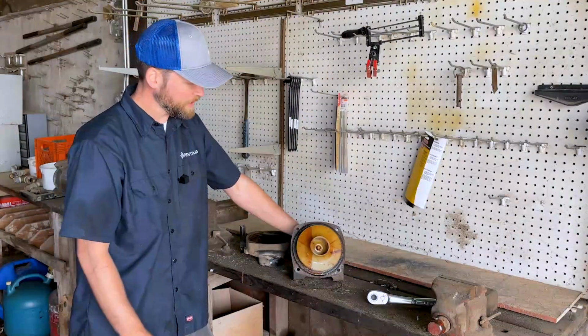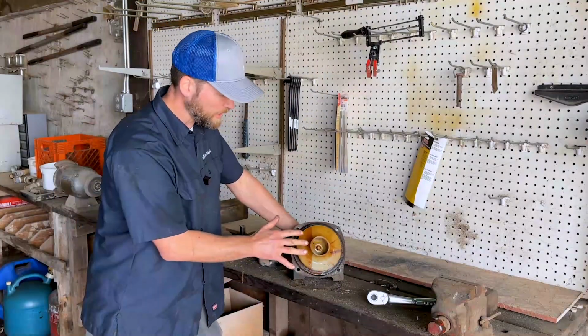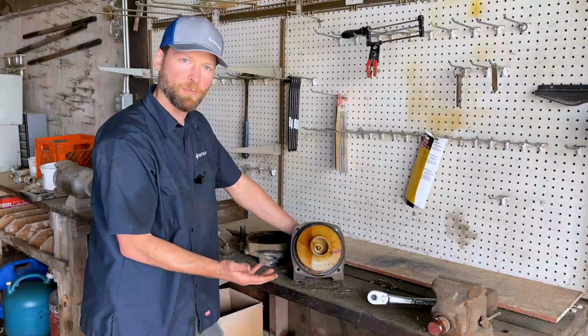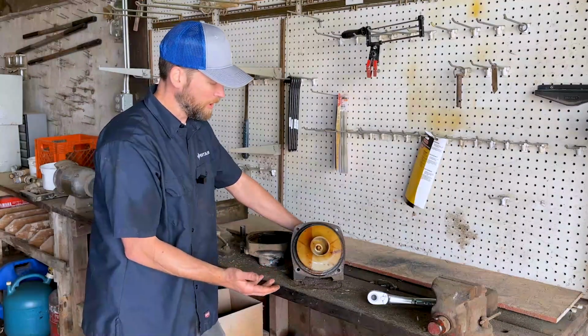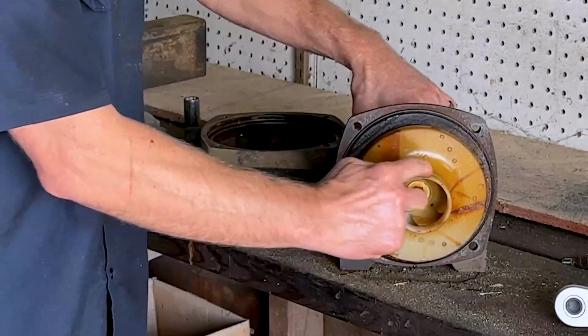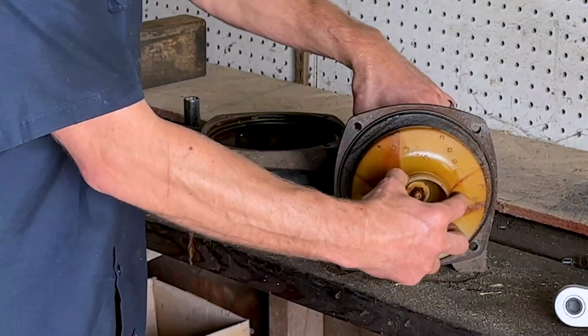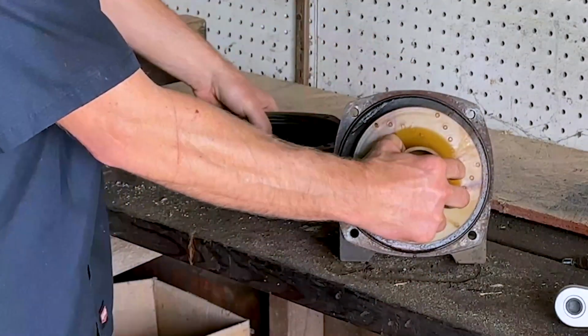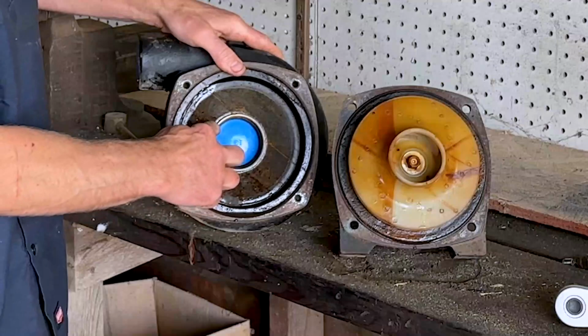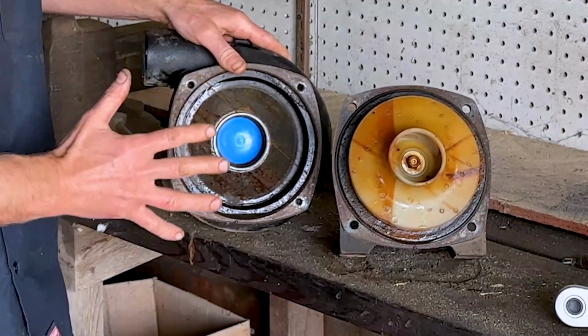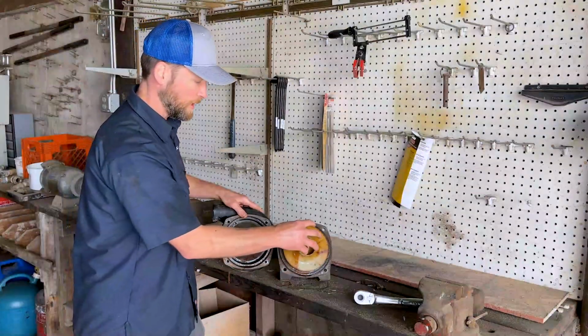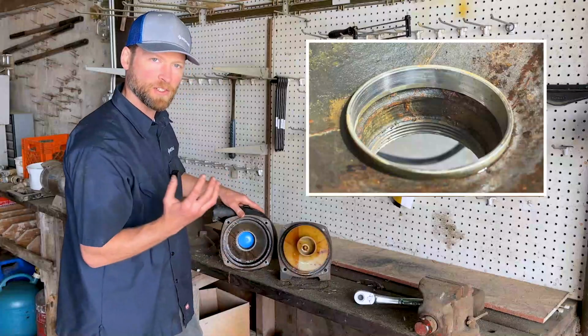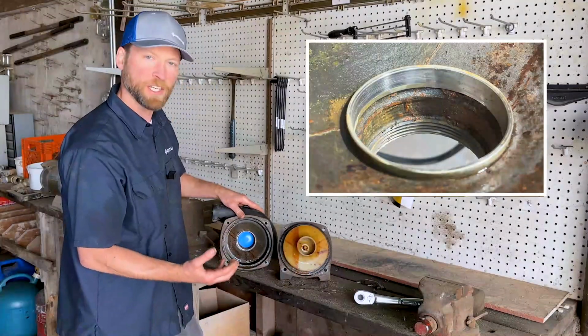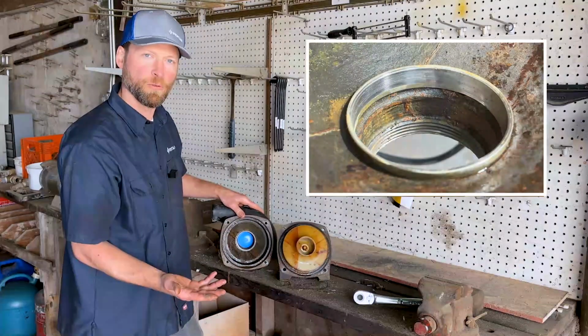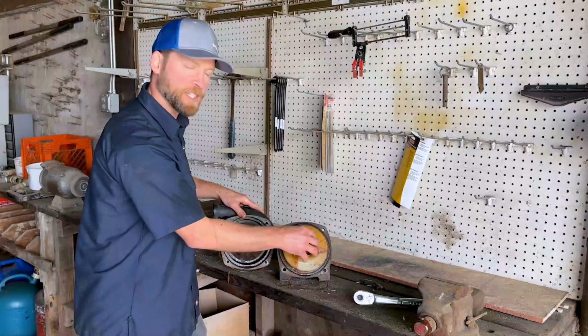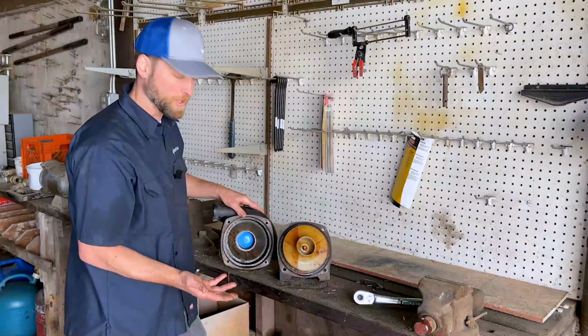All right, so you can see there's a lot of staining on the impeller just from the chemicals that have been going through this pump. What I will show is there's a significant amount of wear around the impeller eye, and that impeller eye mates with the stainless steel wear ring on the front of the volute. And if there's a lot of wear, that'll cause lower performance, that'll cause cavitation, and decrease pump performance. So that's probably one of the contributing factors that led to the low performance on the sprayer.